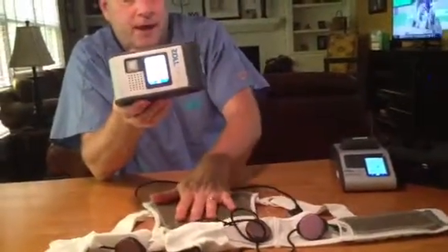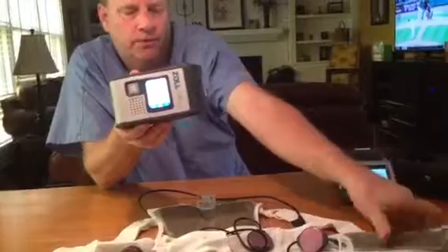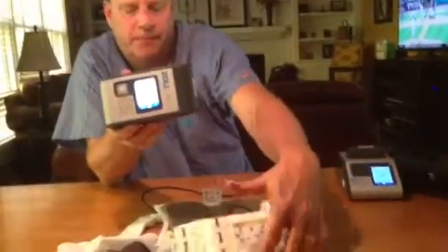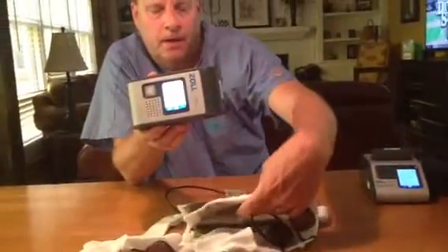Make sure round electrodes touch your skin. Nothing is between the electrodes and your skin. Garment fits snugly. Snug fits the best fit. So it monitors all 4 of your electrodes to make sure they're in good contact with your skin. If you hear a gong and you look down, one of your paddles has interference. Typically the ones on the back aren't an issue because they're nice and flat.